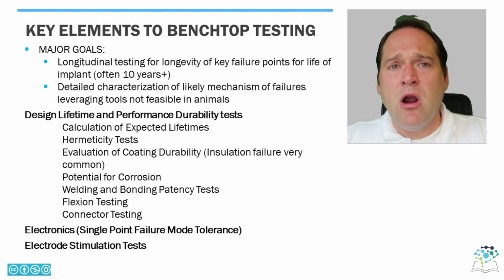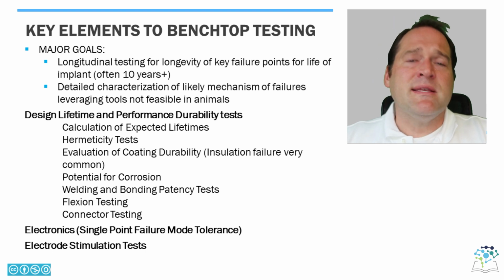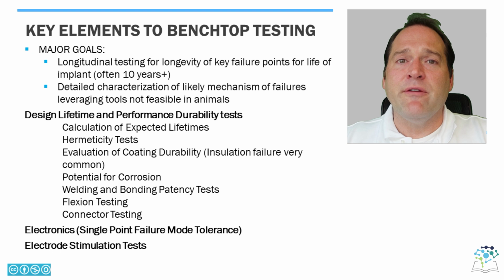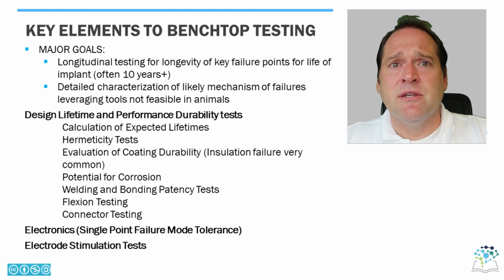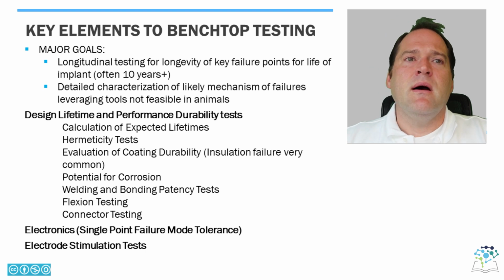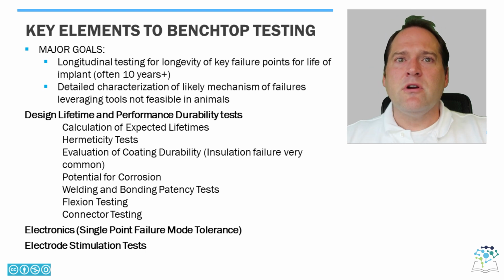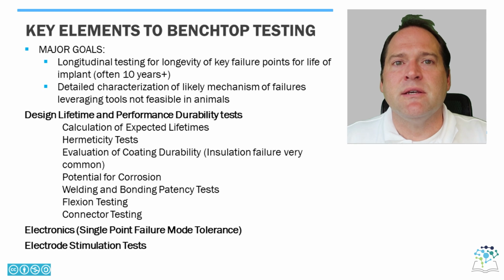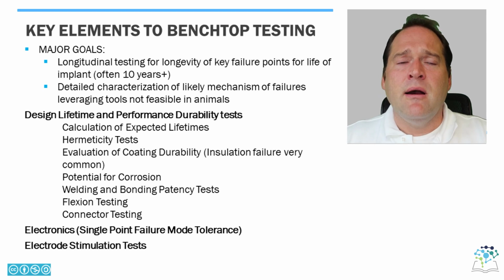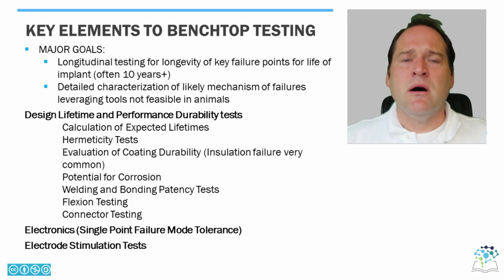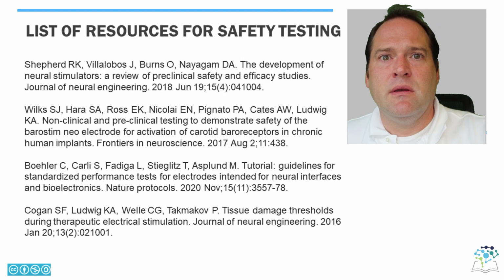And this can actually be a problem in and of itself, because that changes the cost of your device. So given insurance reimbursement rates, if you redesign the device and develop it for single point failure modes, it might change the cost of it, and you can actually change your business case and not have a viable business case. Then finally, another component of this is electrode stimulation tests. That's a specialty of mine, but I'm primarily just going to, in the upcoming slides, point you to really good resources on electrode stimulation safety testing.